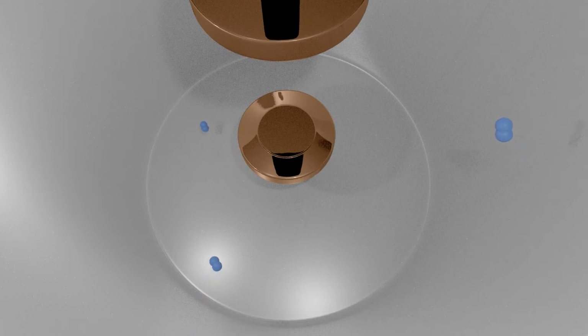So basically they're intermixed, and there are tens of thousands, hundreds of thousands, or millions of gas molecules inside an interrupter that is at very low pressure. Now what the next animation will show you is the internal materials outgas. Every time there's an event, a few more gas molecules are emitted from the metals. These will continually rise in pressure and will eventually get to the point where the breaker will no longer operate properly. The interrupter will no longer interrupt as it's supposed to.